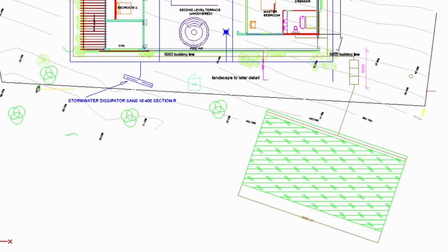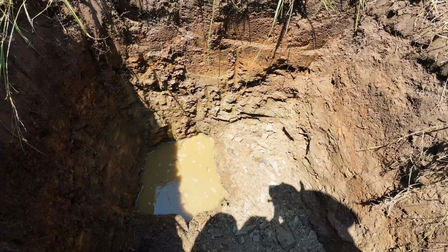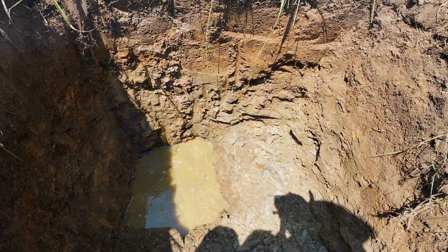So if you need that, we certainly can do that. We'll send a team out there, we'll dig the holes, we'll run the tests. It takes the better part of a day, I'm afraid, because the regulations stipulate that it has to be soaked for 4 hours. So maybe an hour of digging and 4 hours of soaking and travel time on the other side. And of course, then you have to run the tests as well, half an hour per test. And then the holes have to be backfilled and reinstated. So it is pretty much a day's job.